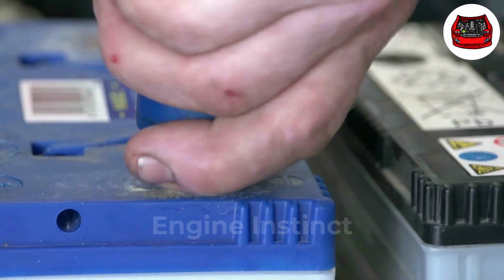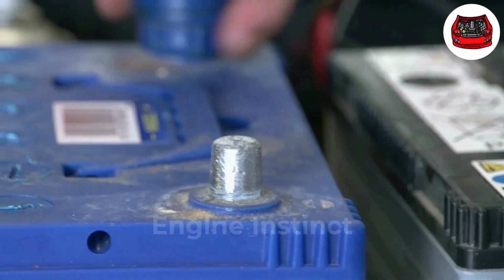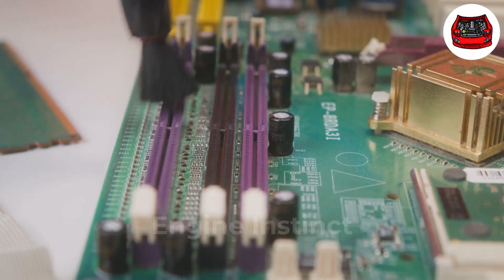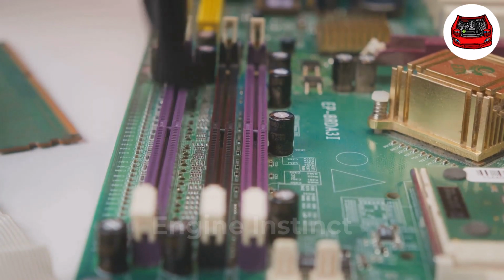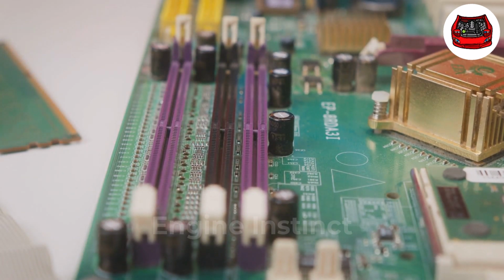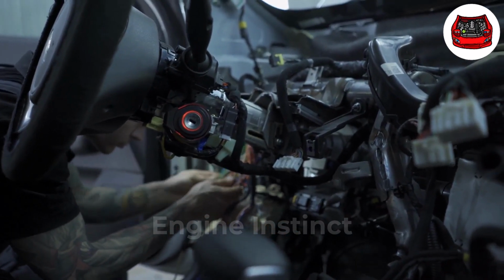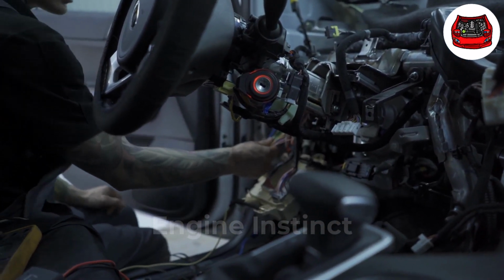Check for visible corrosion, oxidation, or physical damage on all accessible electrical contact points. Clean the contacts delicately, using specialized electrical contact cleaner and appropriate brushes or swabs. Reassemble all components carefully, ensuring proper alignment and secure fastening of all mounting points.